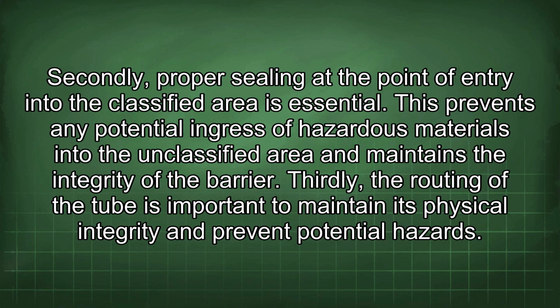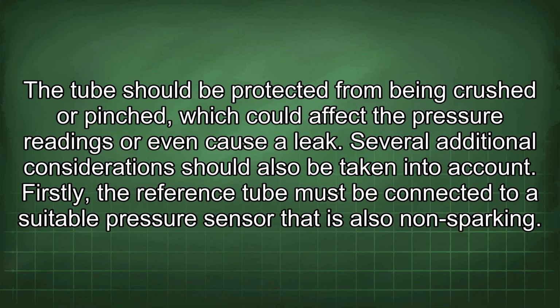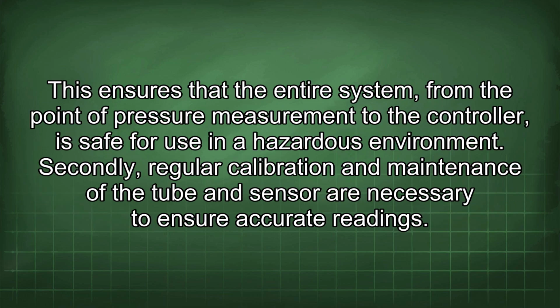Thirdly, the routing of the tube is important to maintain its physical integrity and prevent potential hazards. The tube should be protected from being crushed or pinched, which could affect the pressure readings or even cause a leak. Several additional considerations should also be taken into account. Firstly, the reference tube must be connected to a suitable pressure sensor that is also non-sparking. This ensures that the entire system, from the point of pressure measurement to the controller, is safe for use in a hazardous environment. Secondly, regular calibration and maintenance of the tube and sensor are necessary to ensure accurate readings.